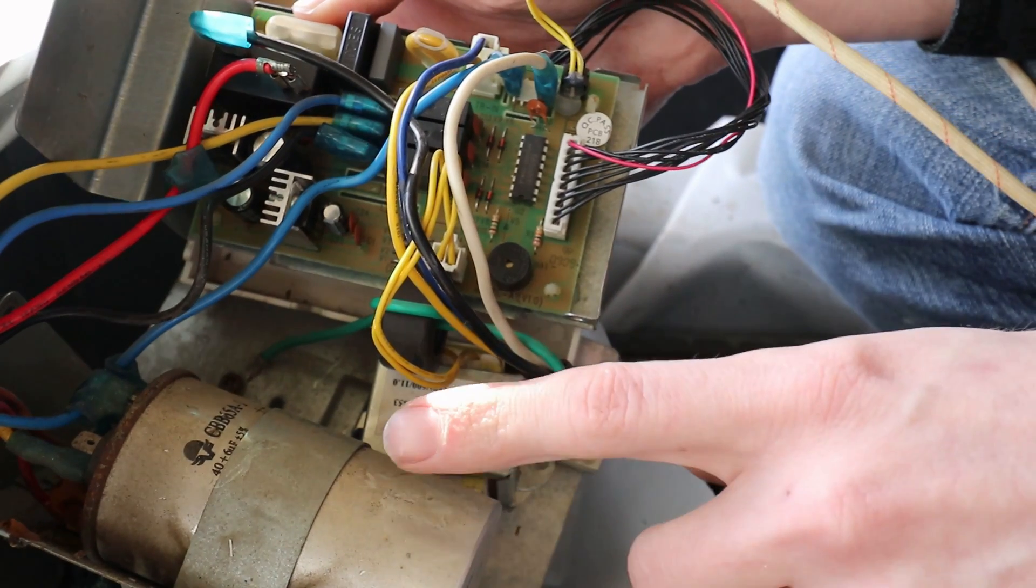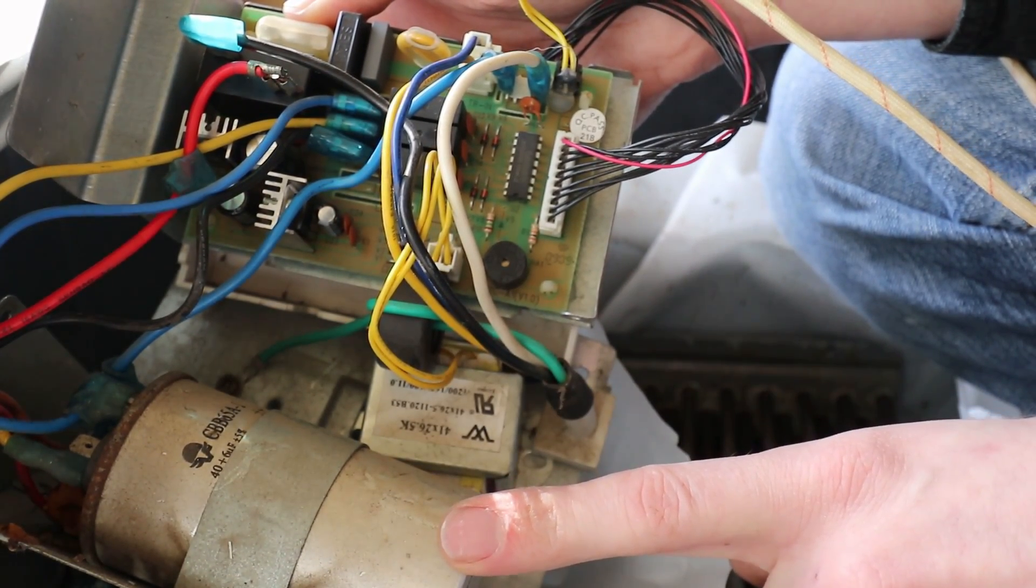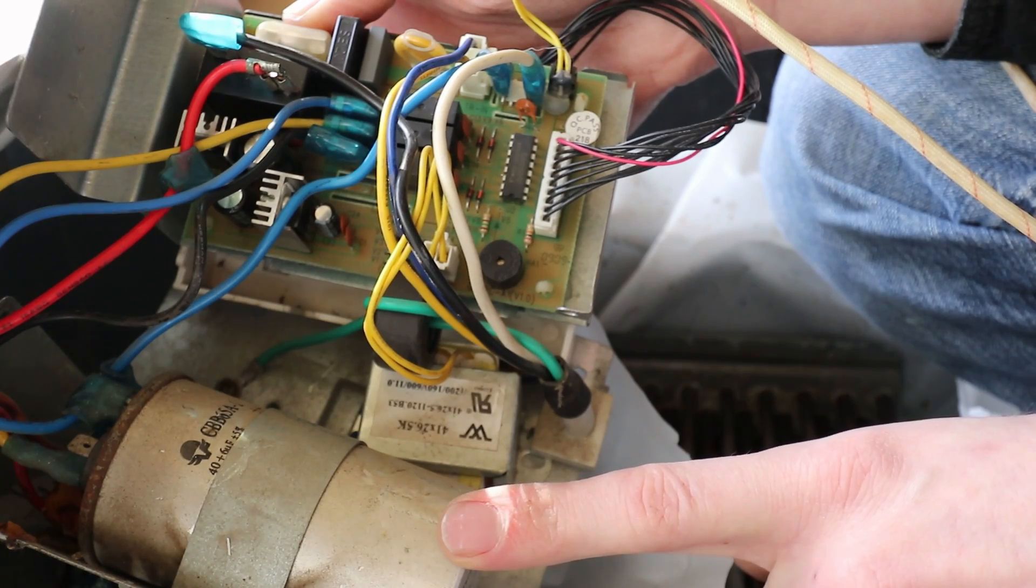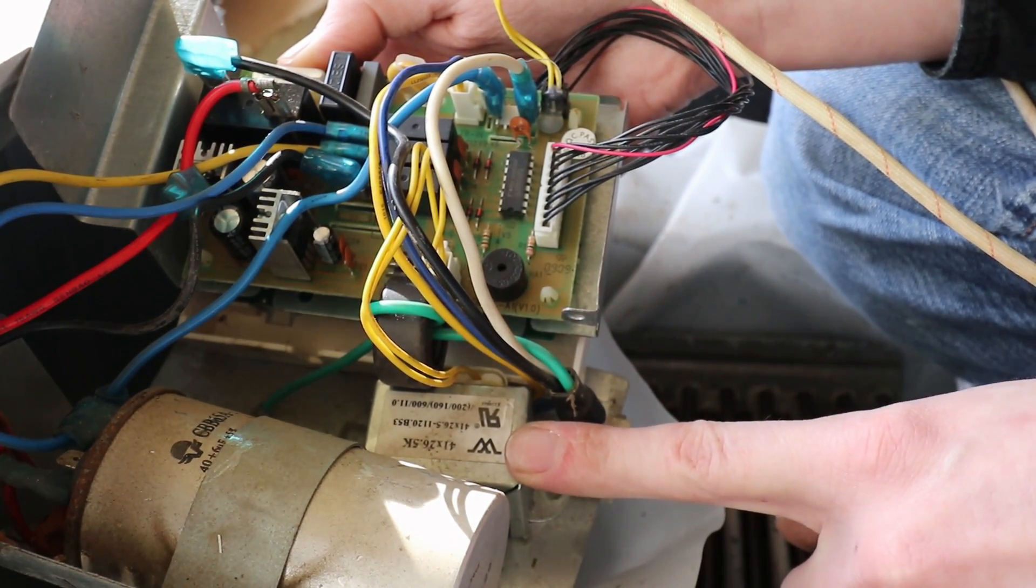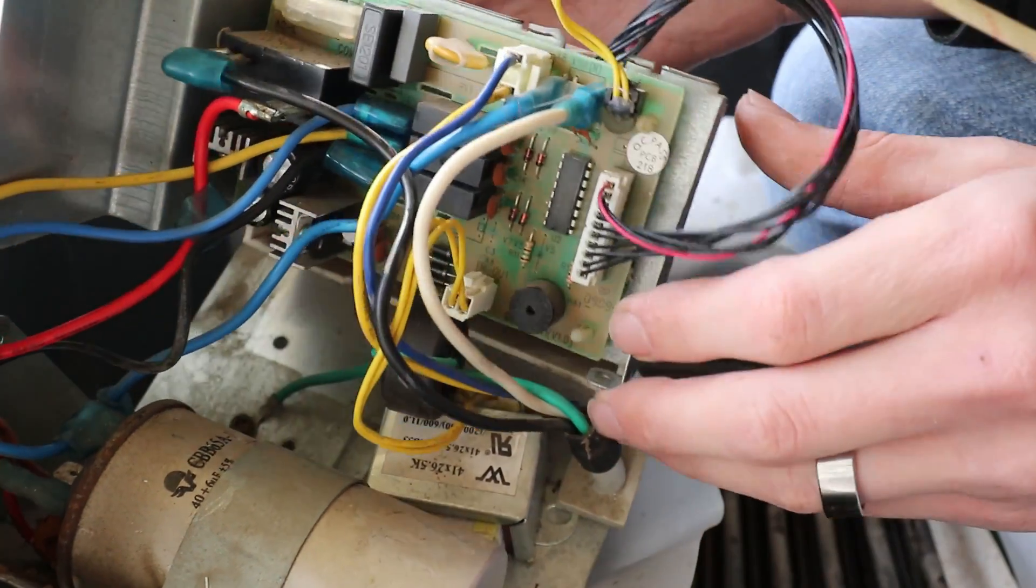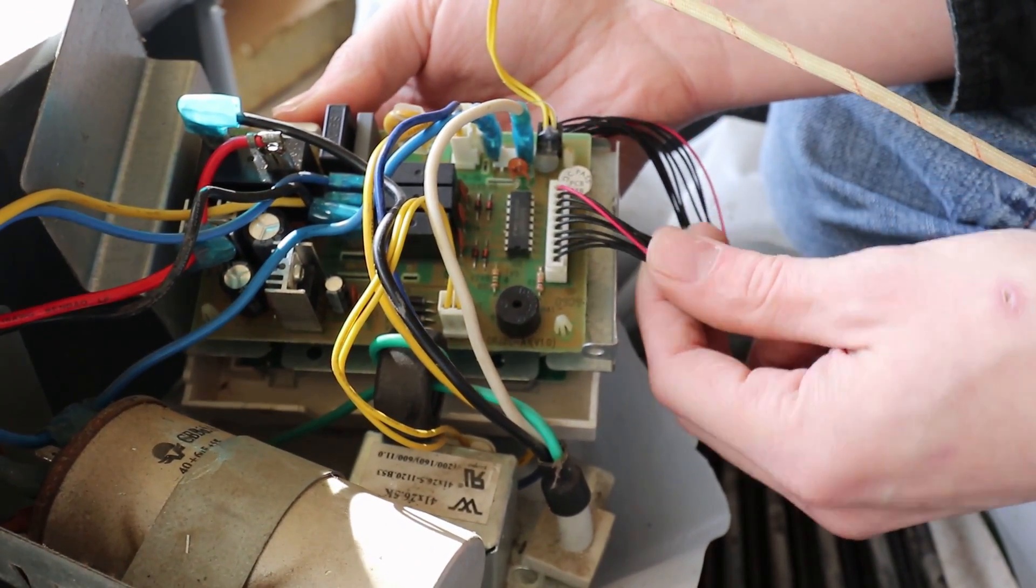Some of the basic components for this: you've got the capacitor here. The fan and the compressor run through this capacitor. You got a little transformer down here. It looks like all this transformer does is drop the voltage in order for the control panel to work. You got wires here for the control panel.